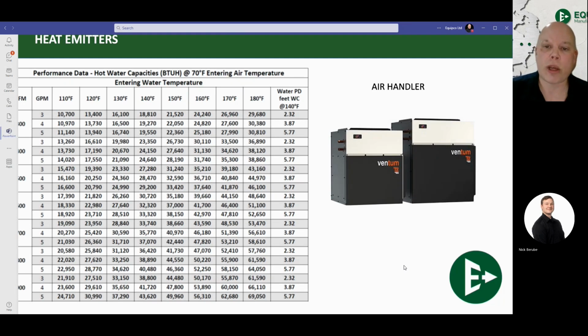Your next step is calculating the head loss through your heat emitter. So let's hop in here. This is my heat emitter. Let's go back and pick on that 16,500 BTU house that we were talking about. We look through our chart, and we want to be underneath that 135 degree mark. We still want to heat that 16,500. Okay, here we go. We heat 130 degree water at 4 GPM, we get 16,500 BTUs. Perfect. That's exactly what we want.